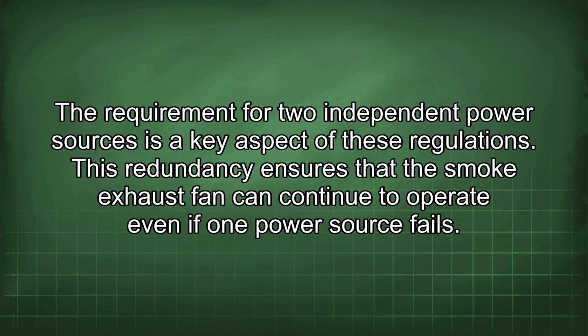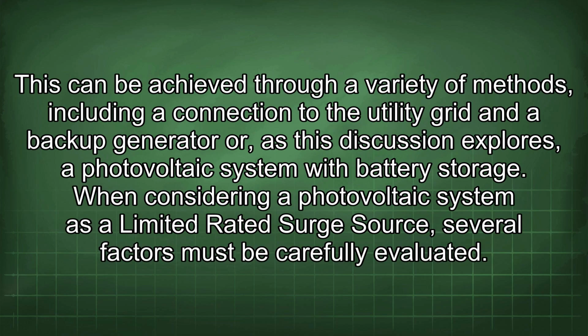The requirement for two independent power sources is a key aspect of these regulations. This redundancy ensures that the smoke exhaust fan can continue to operate even if one power source fails. This can be achieved through a variety of methods, including a connection to the utility grid and a backup generator or, as this discussion explores, a photovoltaic system with battery storage.